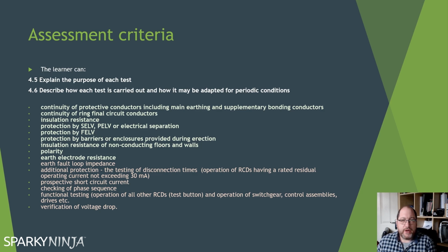If we have something like a 3036 semi-enclosed rewirable fuse, it may be that it just blows up, which can be a danger. So we need to monitor the prospective fault current, and we need to make sure that the breaking capacities of the devices are always within tolerance.